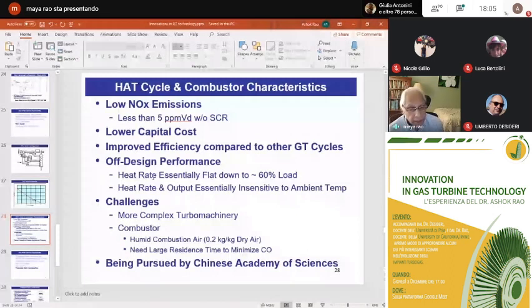Now, this could be a big advantage, especially these days with gas turbines used, as Professor Desideri mentioned, to complement renewables. These gas turbine-based cycles will have to make up the difference when you have less renewable energy available. And this allows you to make up the difference without compromising efficiency. You can go up and down in power output all the way down to 60% without much of a degradation in efficiency. And the other advantage is that it's quite insensitive to ambient temperature. Even combined cycles suffer heat rate and output penalty as the ambient temperature increases.